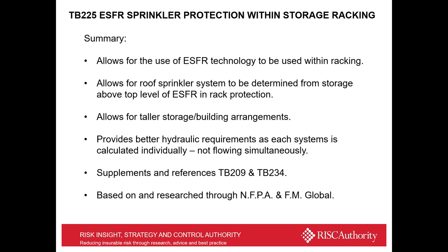You only calculate for one operating at either the roof or the racks, whichever has the bigger hydraulic demand. It supplements and references both TB209 and TB234, and it's based and researched through NFPA and FM. So those are the benefits of ESFR if it can be applied to the warehouse. But again, as mentioned earlier, all systems should be agreed with the insurers.